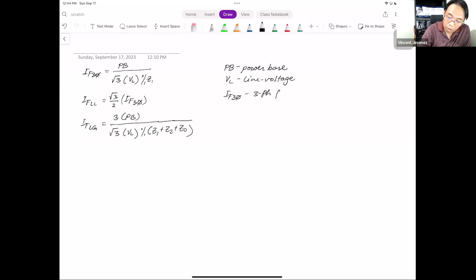To break this down: PB means power base, V line is line voltage. IF 3-phase is the three-phase fault, or what we call a symmetrical fault. IF line-to-line is the line-to-line fault, one type of unsymmetrical fault. And IFLG, line-to-ground, is the line-to-ground fault.